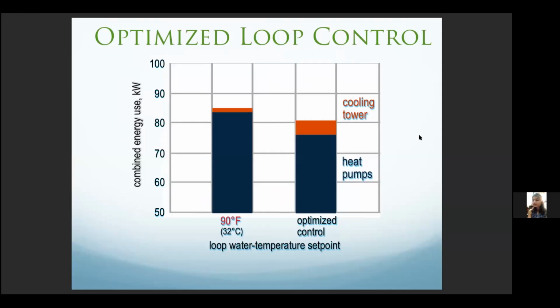Optimized loop control. Now in this scenario, we're using a cooling tower and heat pump system, where in the first scenario, in the first graph over here, we are running the cooling tower not as hard, as you see from this red line at the top, and we are running the heat pumps super aggressively. Whereas in the second scenario, we've optimized the control, where by running the cooling tower harder than before, we are able to save energy on the heat pumps. So if there's more cold water being dumped into the heat pump loop, you may be able to save energy on the heat pumps from the perspective that they may use that colder water to increase efficiency.